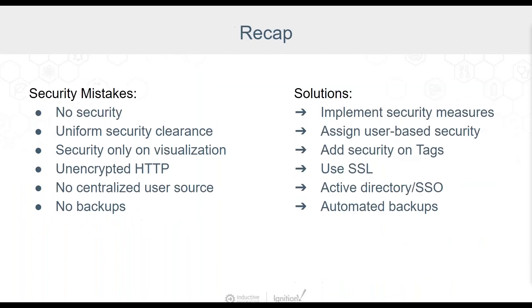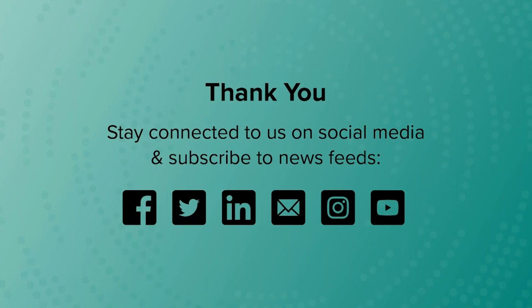Now back to Kent for a recap. The first mistake is having no security measures — the solution is to implement the security practices we've covered. The next mistake is having uniform security clearance, which is solved by assigning user-based roles so that security is managed on a person-by-person basis. Next is having security only on visualization — that's not enough; you need to secure your tags themselves. Having unencrypted HTTP isn't sufficient either, so use SSL to keep all information encrypted. If you don't have a centralized user source, use Active Directory for authentication, and increase security further by implementing two-factor authentication. Finally, if you don't have gateway backups, use automated backup solutions either on a single gateway or at an enterprise scale.